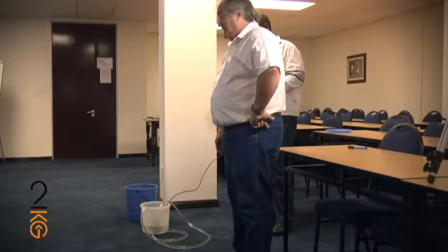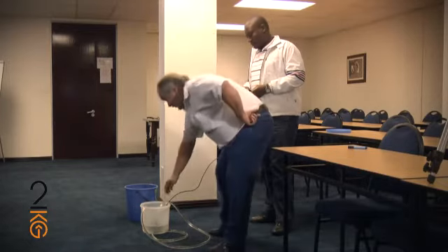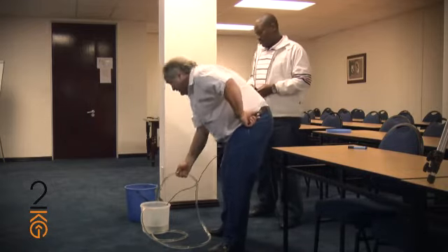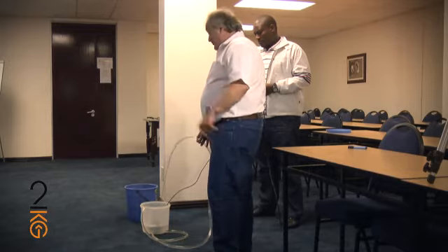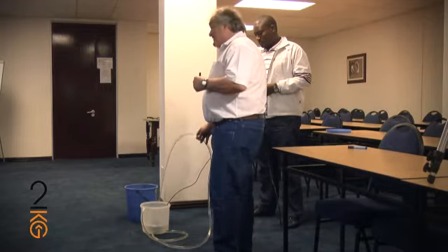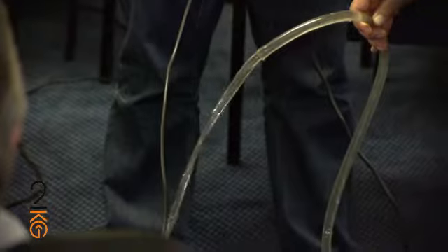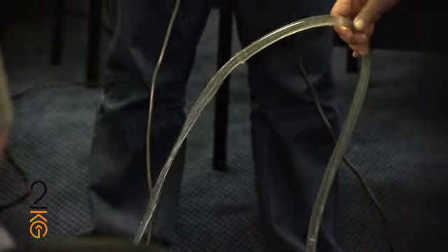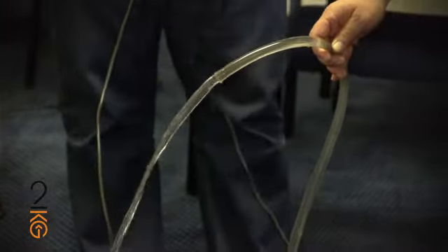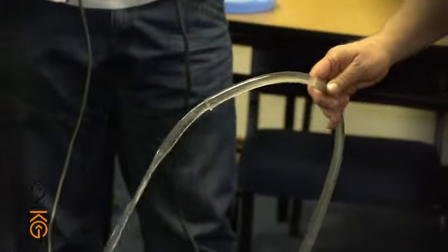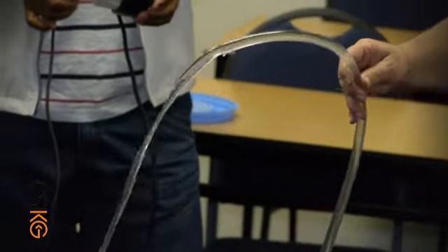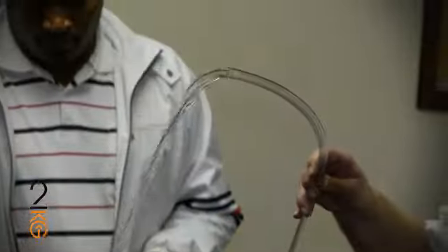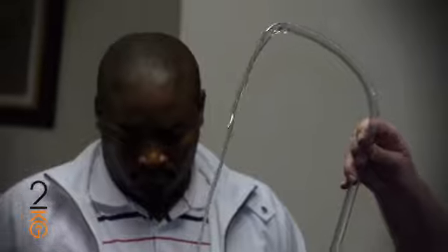This pump is operating at one spot on the curve. But if I increase the elevation to here, now we're lifting the liquid. And because some of the energy is involved in elevation, less energy is available for flow. So flow is going down as head rises. As I raise the elevation, we're migrating on the curve.